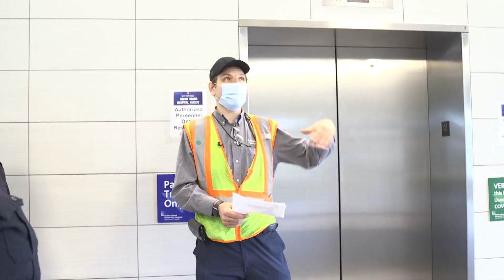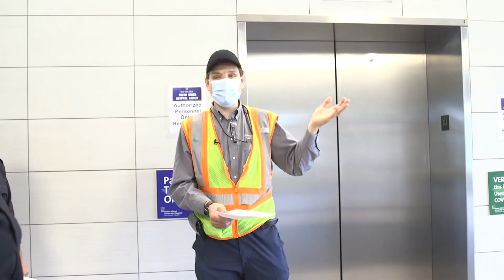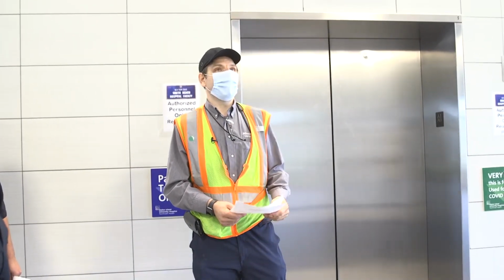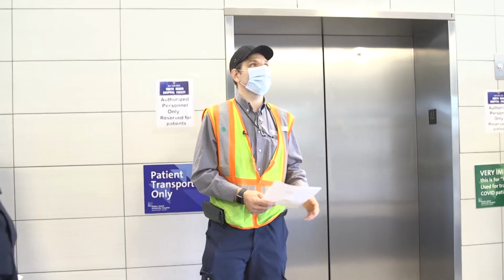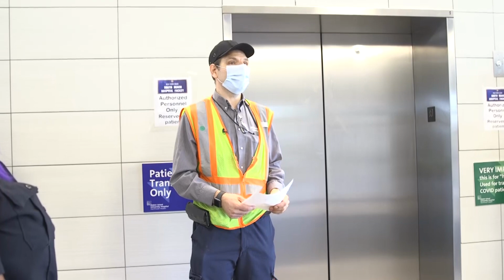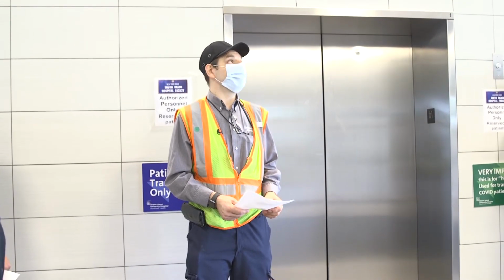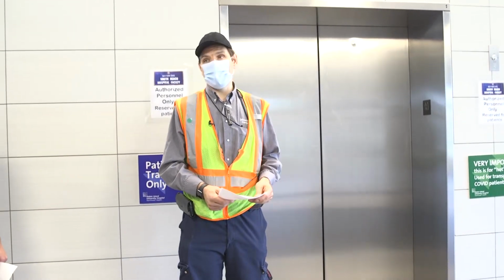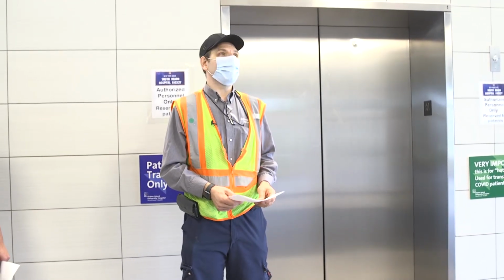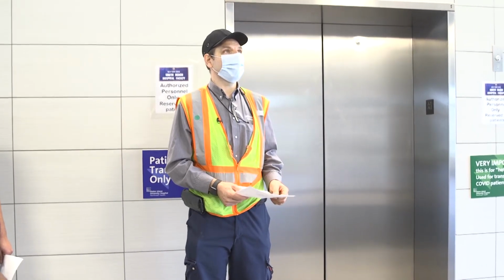Only this floor sends to the second, the alternate floor, to not send it where the fire is. That's the only difference. So on every floor you have these two smoke detectors which recall the elevator. This is very important. If these smoke detectors are activated, the elevator will not work, so you want to make sure these 2 smoke detectors are in good condition.